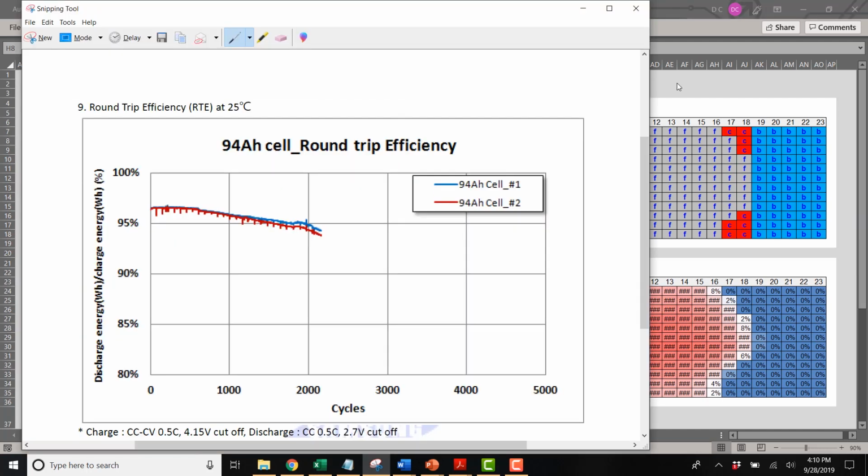Pretty cool. The next exciting upgrade, we are including round trip efficiency degradation, meaning that as the battery gets older, it's less and less efficient. So as the system gets older, your round trip efficiency gets worse and worse. For an AC coupled system, you might start off with a round trip efficiency of about 88%, but after 10 years, your round trip efficiency will probably go down by 3 to 4%.